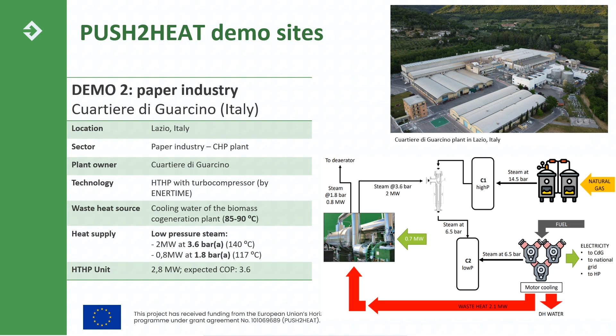The thermocompressor would deliver a higher pressure steam to introduce it directly in the low pressure line of the processes. But another option, which the project partners are working on (I'm not personally involved in this), is to also try to identify specific processes that could use this lower pressure steam directly, which would increase the overall efficiency of the system. We are still working on this, and we'll see in the upcoming months which is the final solution. Here the expected COP is around 3.6, which is a very interesting COP. This is an overview of this demo site.